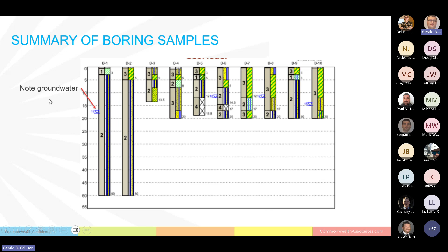And of course, noting that groundwater is present, so what did we get? They gave us these resistivities in ohm centimeters. So we're looking at this, and we can see what we're seeing at different heights, and we're seeing resistivities in the thousands. We're expecting maybe 200 at 5 feet over 300, conservatively that would be the upper end of what I'd expect. And we're seeing readings in the 3,000s on all of these. This is way off of what I'm expecting.